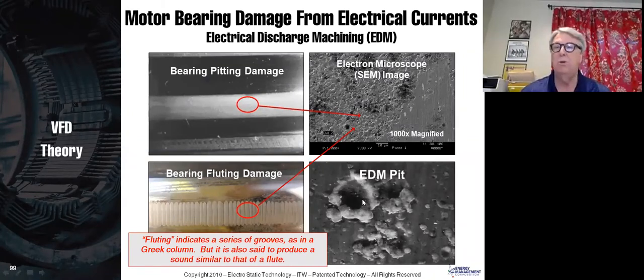You can't see that with your naked eye, but these little discharges, electric discharge machining, or EDM, create this pitting in your bearings. To the naked eye, the pitting looks like this. It just kind of makes that shiny bearing more of a matted type of finish. And if it gets really bad, then it turns into fluting. Once you get fluting, which is down here on the lower left, because it looks like the fluting on a Greek column of a temple or something, then your motor is going to be really noisy and it's on the verge of bearing failure.